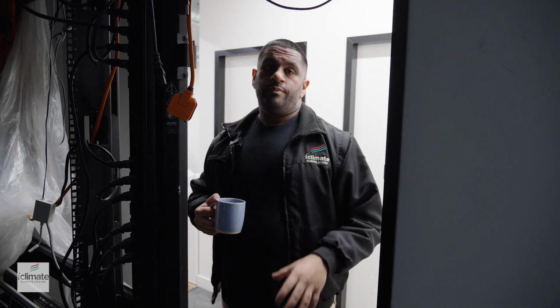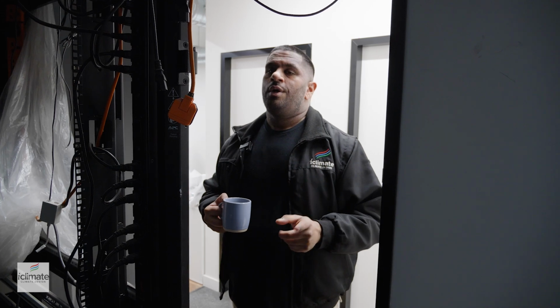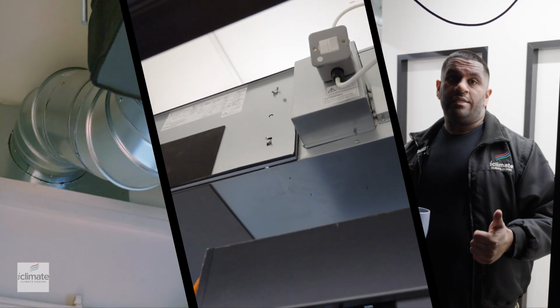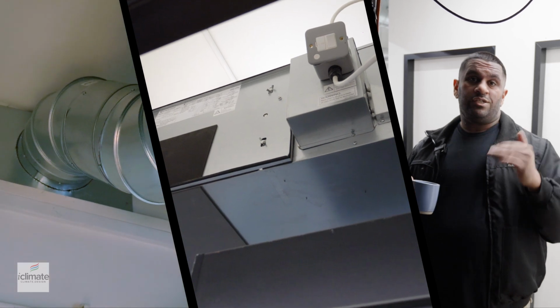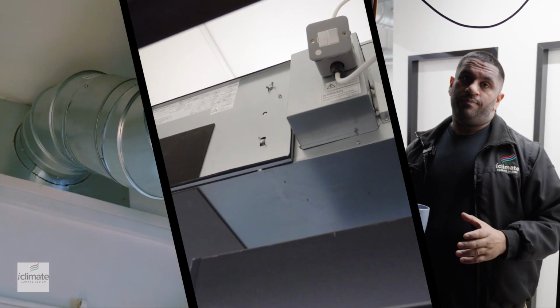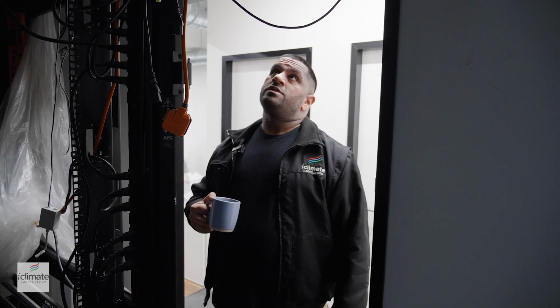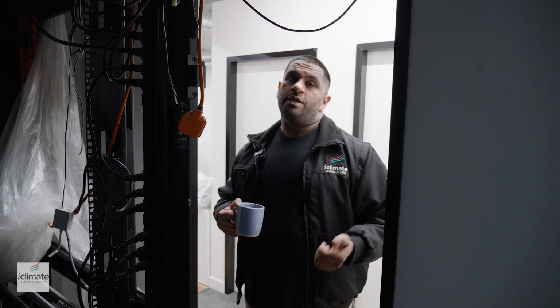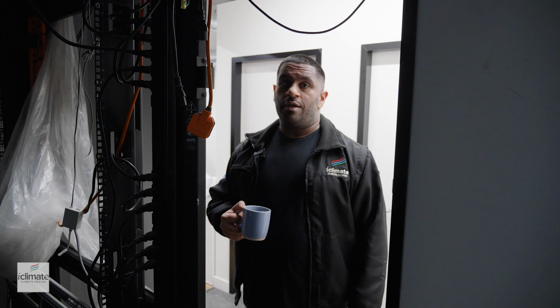So we're in the server room. There's no light because the PIR needs to be relocated by the client's contractor, which they're going to do. But let's talk about the MVHR unit, right? So they have a filter element inside them, and there's also a cross heat exchanger, like I mentioned, the heat exchanger element, which you have to leave sufficient space on the access panel to come out once a year. We inspect it and change it depending on the conditions of the air inside and the quality.